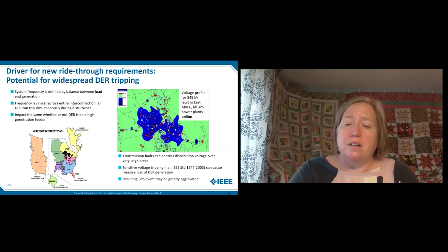So we have tripping requirements and we have ride-through requirements in 1547-2018. Ride-through is really important. It's not a setting. It's not part of protection. It is a capability, a performance capability of the DER. Language includes it shall ride through for at least so many seconds.